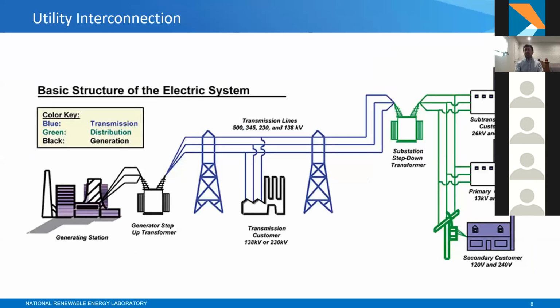But most of this is all designed to make sure that you're installing these devices in a way that's safe for the consumer and the utility grid. And the utility grid is important to consider because there is a lot of equipment on this system that goes from the generator to your home and many different devices in between that the utility needs to make sure is operating all of the time and can always provide electricity. So there are a lot of considerations up and down this whole spectrum here, from generation to transmission, substation, and distribution before it gets to your facility or building's load center.